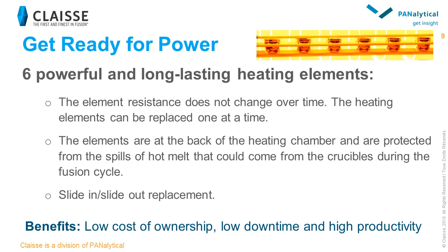One of the advantages of TheOx Advanced is its powerful and long-lasting heating elements. We kept the same sturdy and reliable heating elements in this new version. Since their resistance does not change over time, they can be replaced one at a time without changing the heat distribution inside the furnace. Also, they are located at the back of the crucibles in the heating chamber, meaning they are protected against spilling of hot melt from the crucibles during the fusion process. There is virtually no need to replace the heating elements even after years of operation. However, if needed, the user can easily slide them out from the top of the heating chamber and slide new ones in.